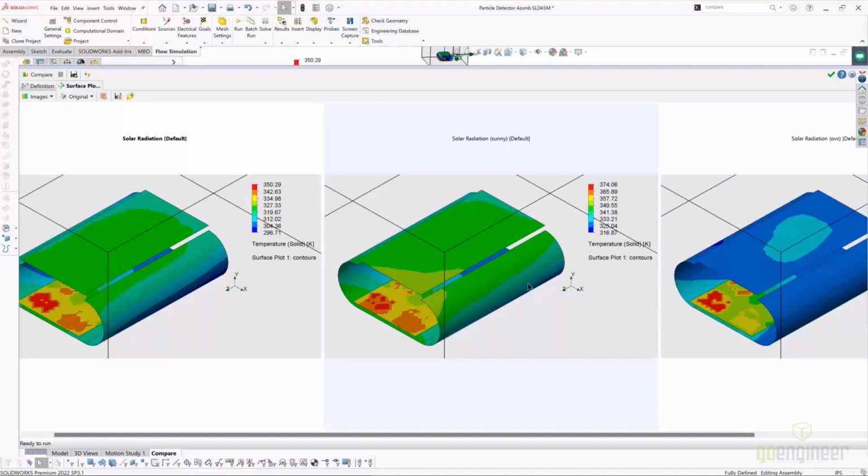So this could be something that we can go to our circuitry or our engineering team and say, hey guys, this is a little concerning. If we run this at a very, very hot day, we may need to make a screen that goes over this or enclose this a little farther so that glass is kind of able to push back some of that radiation so that it doesn't affect the particulate particle counters, because that will affect the accuracy of our particulate data.